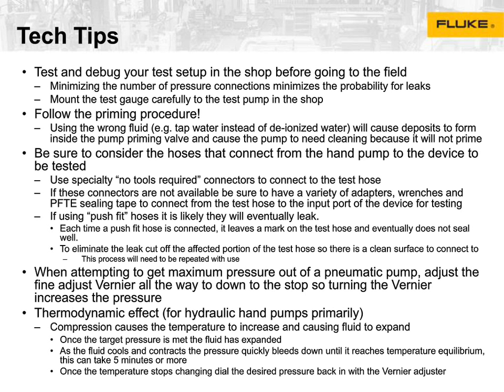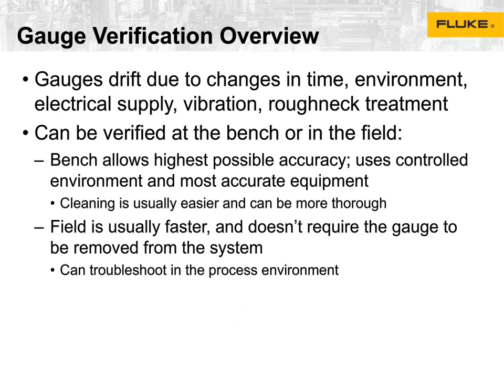Okay. Moving on, we're going to talk about gauge verification. At a high level, the gauge verification procedure, we talked about why gauges drift already, and so I'm not going to recover that, but they can be verified both on the bench or in the field. Benches give you some advantages like really high accuracy. You can use more accurate equipment because you're at a bench.